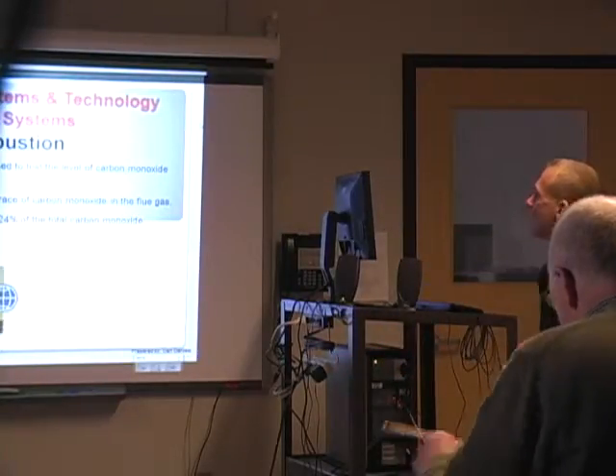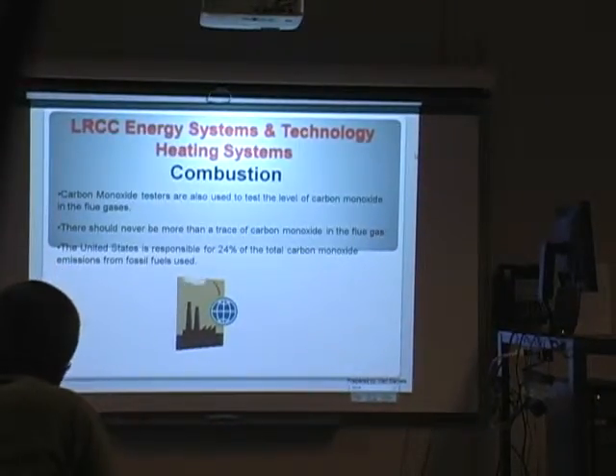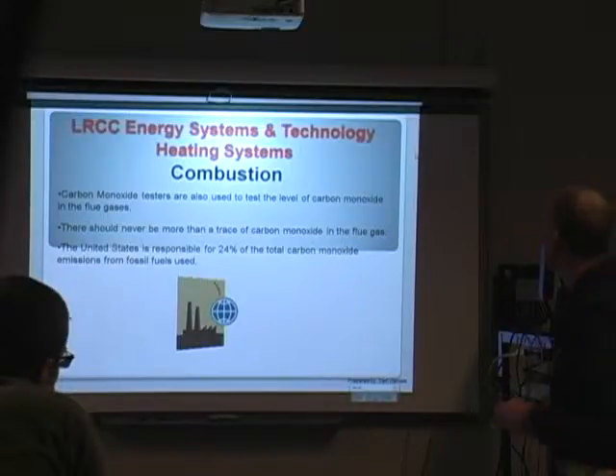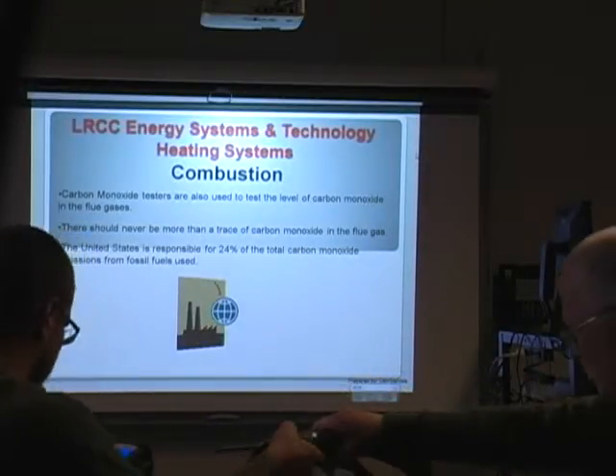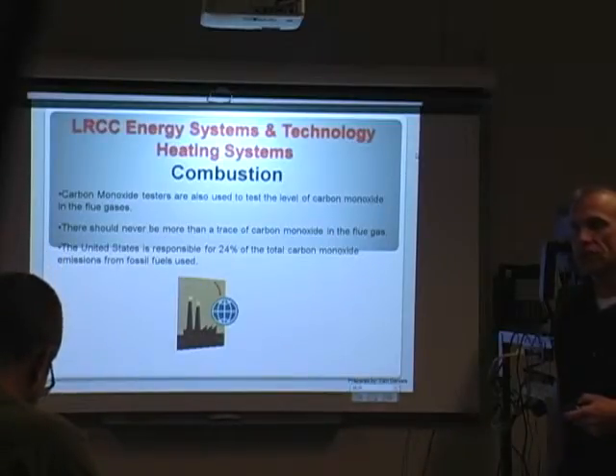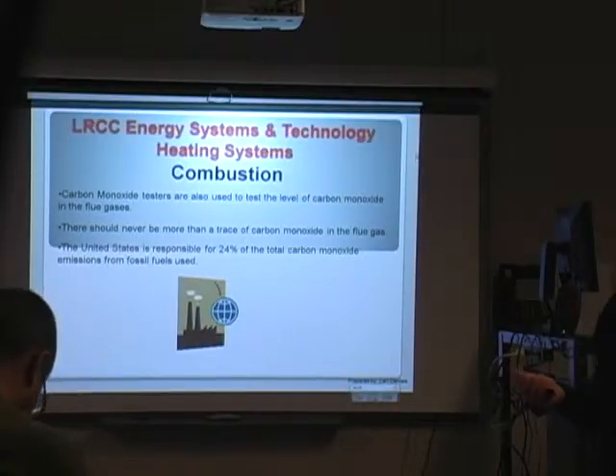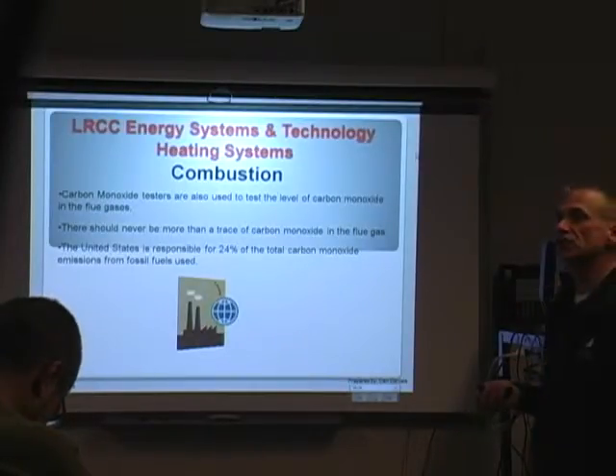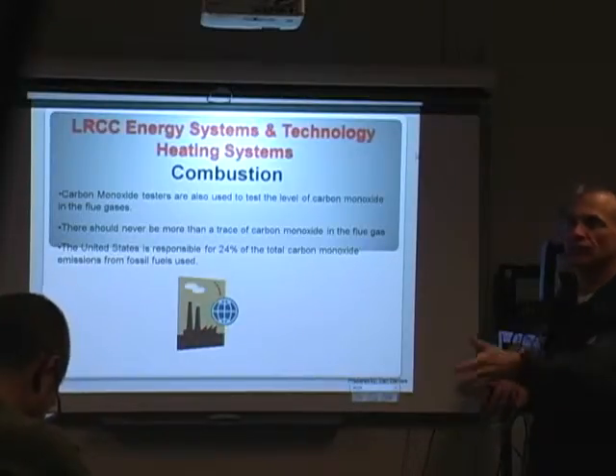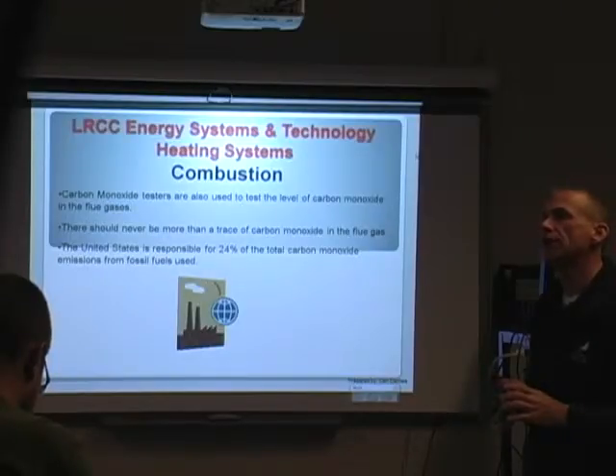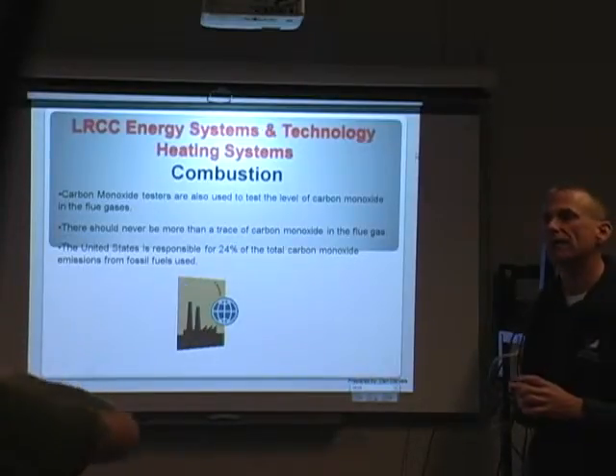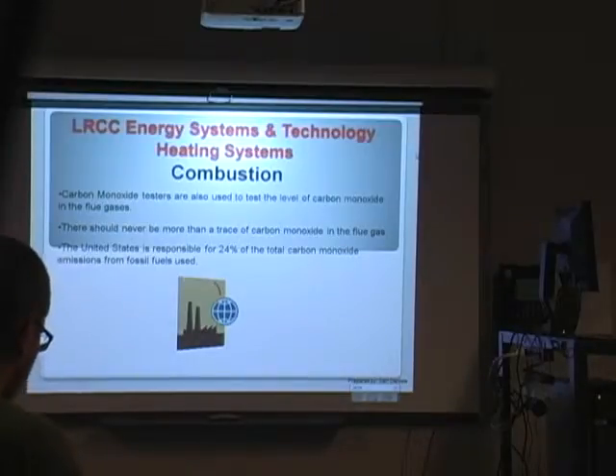Some of the things we test for include fuel pressure coming in, and draft — because overdrafting will give us excess air. We never measure for smoke on propane or natural gas because they don't produce significant smoke. However, oil, coal, and especially wood produce a lot of smoke because of their carbon content. For those fuels, we use a separate smoke tester — a long handheld vacuum that draws a sample through a white screen, which we then compare to a chart to determine the percentage of smoke. We also test for carbon monoxide, carbon dioxide, and excess air.